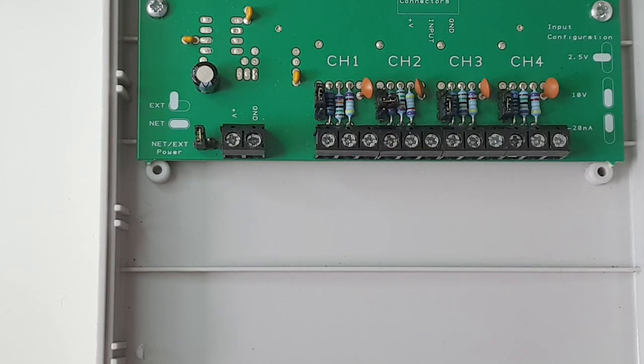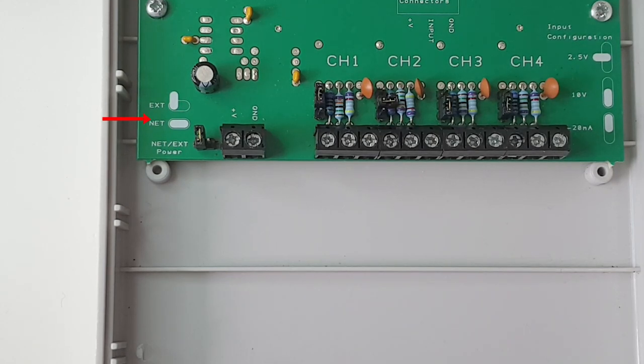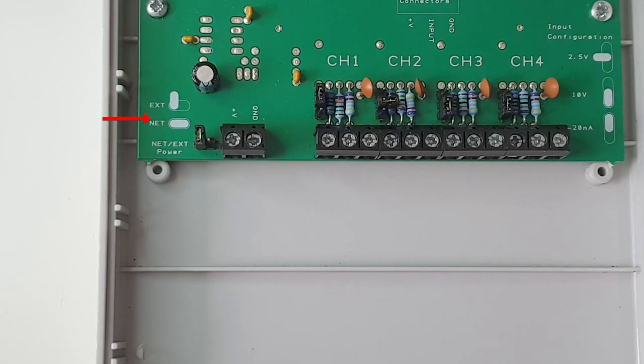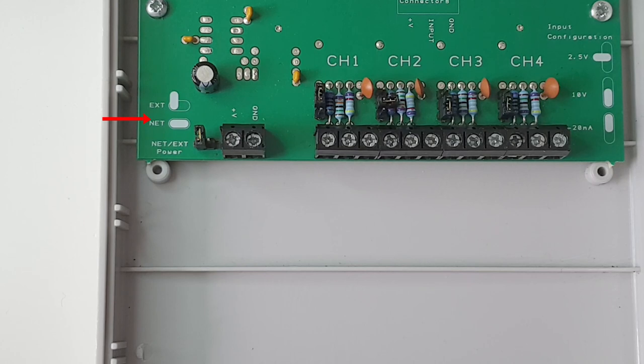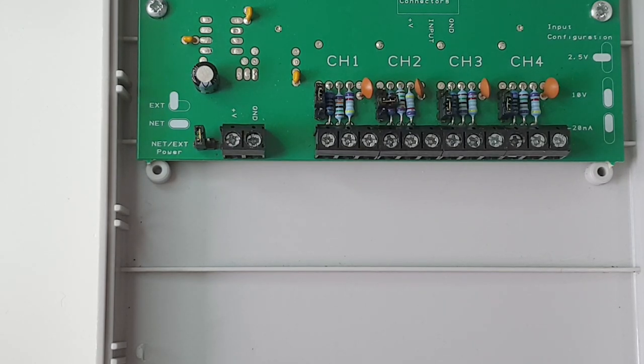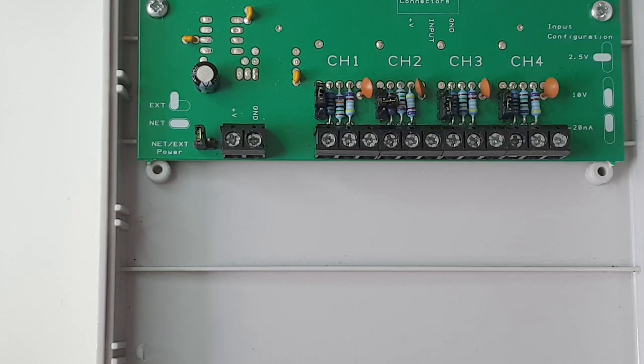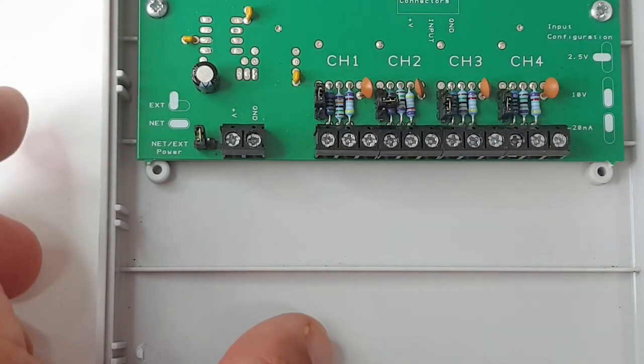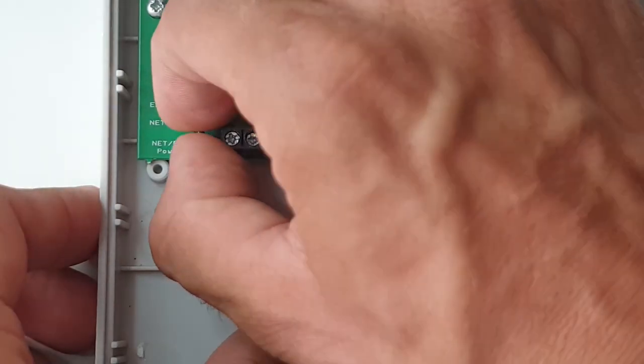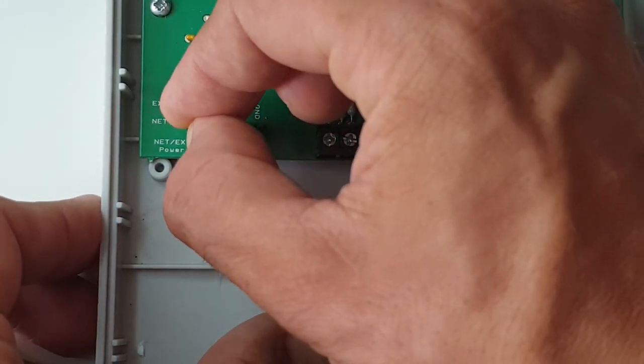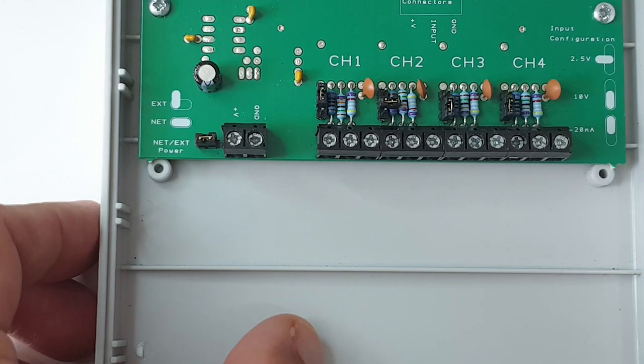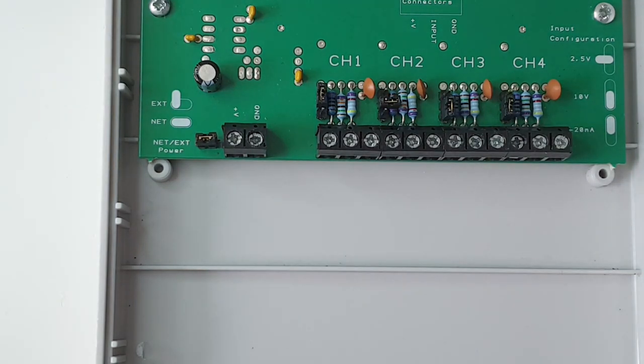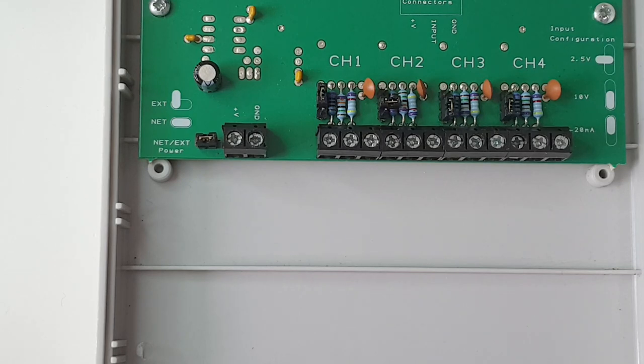Now if you look at the left hand side, you can see that you can power your sensors either from the environment network or from an external power supply, which would then plug into the screw terminals. So say for example you wanted to use the environment network voltage to power your sensors. What you do is you get the jumper out and you would then short the two pins over here like that. Now that would mean that the environment network cable, which carries the voltage from the data logger, would then power your sensors.